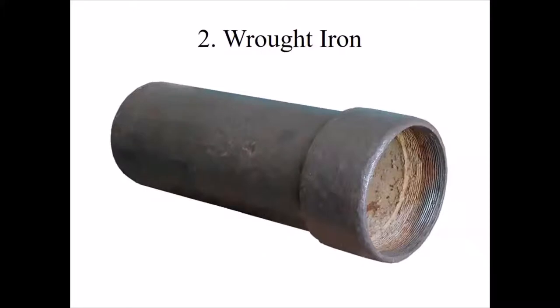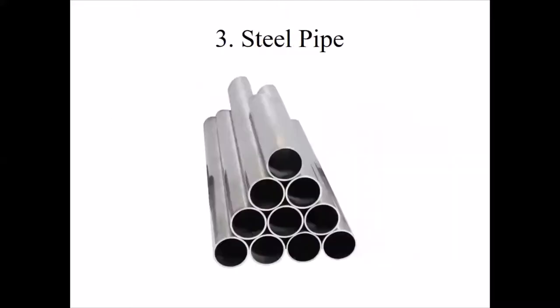Wrought iron pipe has nearly the same properties as cast iron pipe. Wrought iron pipes can be easily cut and threaded but are costly and not very durable. These pipes are affected by corrosion and are generally used inside buildings. They may be recommended for main pipelines if galvanized with zinc.